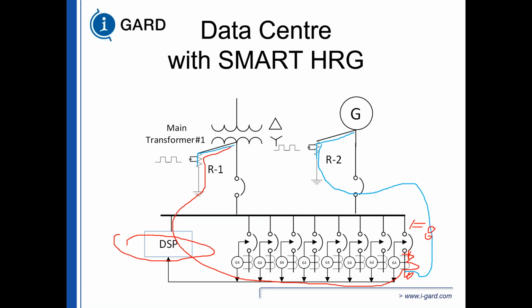You have a central location, but the feeder modules can act independently as well. So if you get a second fault here, and let's assume this was a data center, so this was protecting your main chiller, and if the chiller goes down, the entire system is going to have to be shut down. And this is feeding the cafeteria. So if you have a choice between the cafeteria going down or the main chiller going down, you're going to choose that the cafeteria is going to go down.